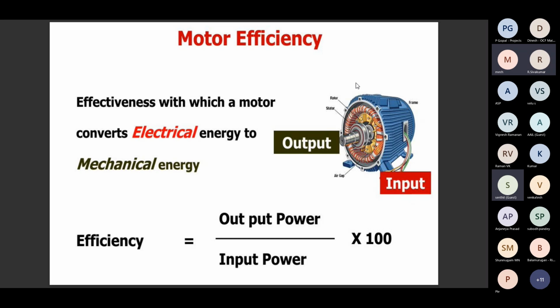This is the actual fact, because the nameplate indicates 7.5 kilowatt or 10 HP, whichever was mentioned, and it represents the shaft power only, not the input power. If you want to calculate the exact input power, take the nameplate rated kilowatt divided by the efficiency. This is a simple example: a 10 HP, 7.5 kilowatt, 91.2% efficiency motor can take up to 8.2 kilowatt. Based on that, you can calculate the motor efficiency. Efficiency is nothing but output power divided by input power.